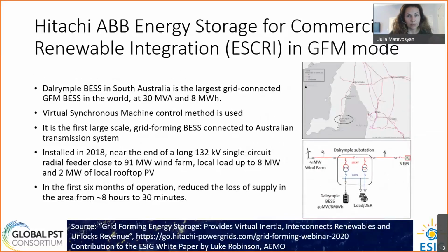So the next example is the Hitachi ABB energy storage in South Australia. This is the largest grid-connected grid-forming battery in the world that at least we are aware of. It's 30 MVA, 8 megawatt hours. It also operates with a virtual synchronous machine control method. It's the first large grid-forming battery connected to the Australian transmission system.